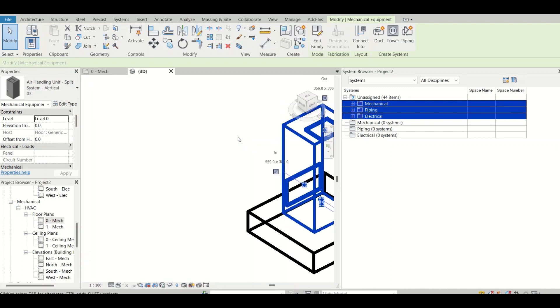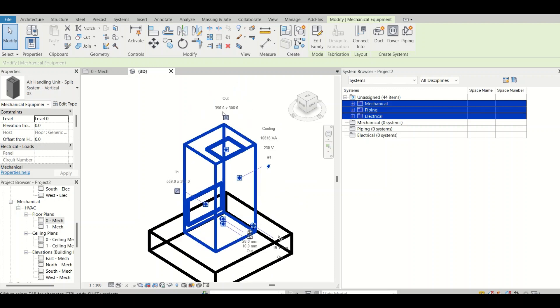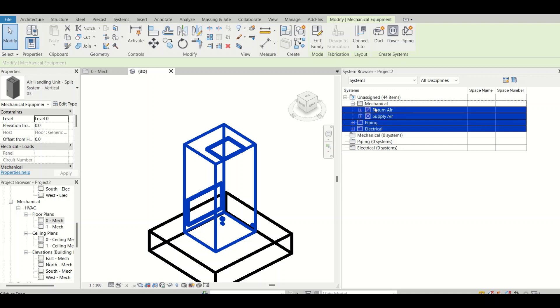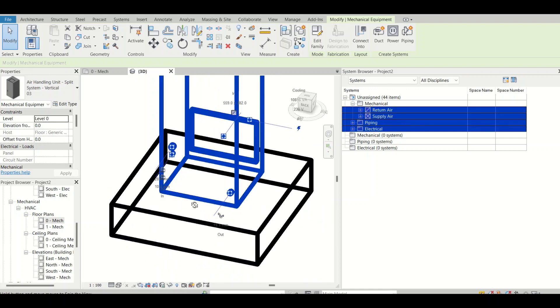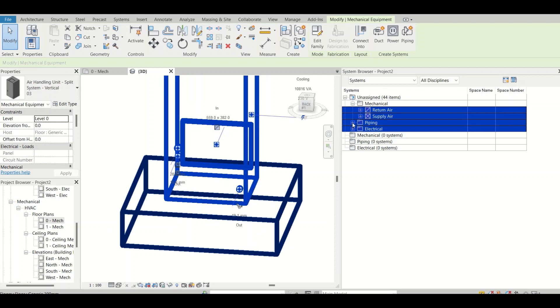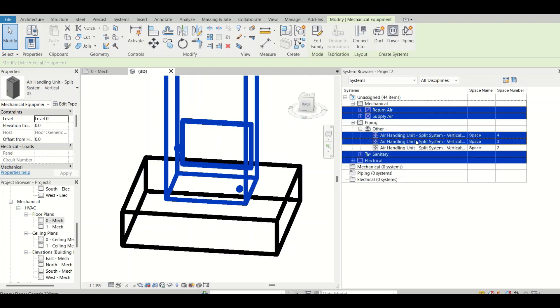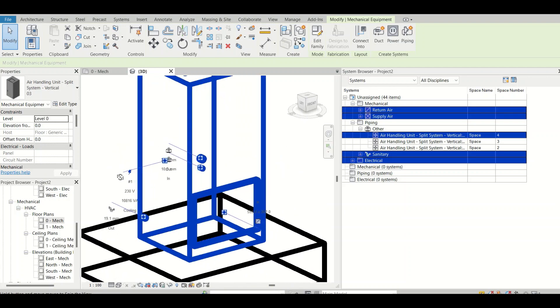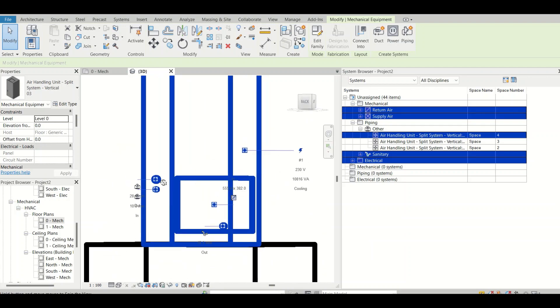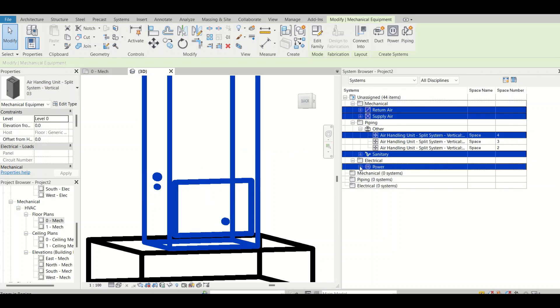The AHU appears under all three categories — mechanical, piping, and electrical. It should come in mechanical because it's part of HVAC. If I show it in 3D, it has multiple connectors — return air duct and supply air duct — which is why it comes under the mechanical tab. It also has chilled water and sanitary connections, so it appears under piping. And since it has a power connection, it shows under the electrical tab as well.